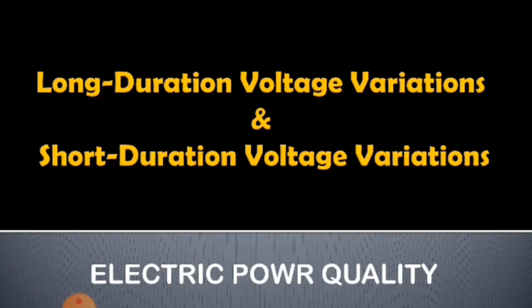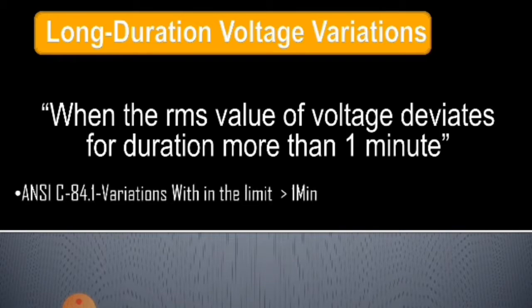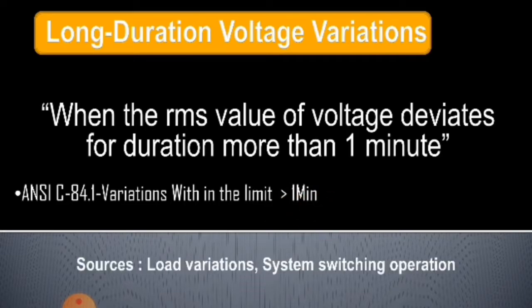Regarding the long duration voltage variations, when the RMS value of voltage deviates for a duration more than one minute. According to the American National Standard Institute C84.1, which specifies the steady state voltage tolerances expected on your power system, a voltage variation is considered to be long duration when the ANSI limits are exceeded for greater than one minute. The sources or causes of long duration voltage variations are load variations and system switching operations.